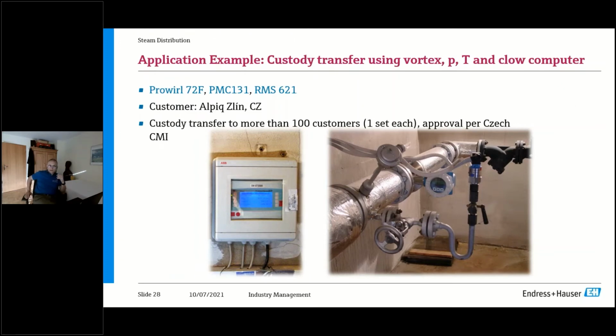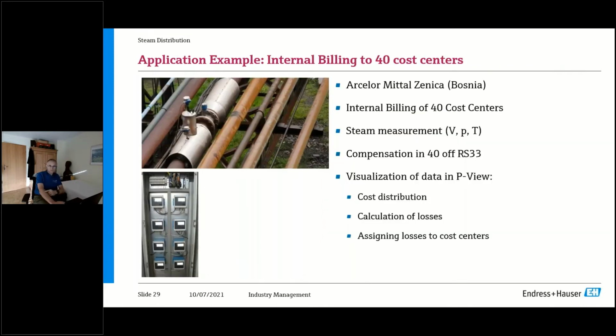So here we have a nice application example. First, that's an example from Czech Republic. The Czech Republic is one of the very, very few examples worldwide where you have a national custody transfer standard for steam. Because keep that in mind, there is no OIML standard for steam right now. Which is, of course, a stupid thing, because you often pay for steam, you get charged for steam, but there is no OIML available. But in Czech Republic, it's slightly different. Our meters are certified for this national approval, the CMI, the Czech Metrology Institute. We have those approvals available.